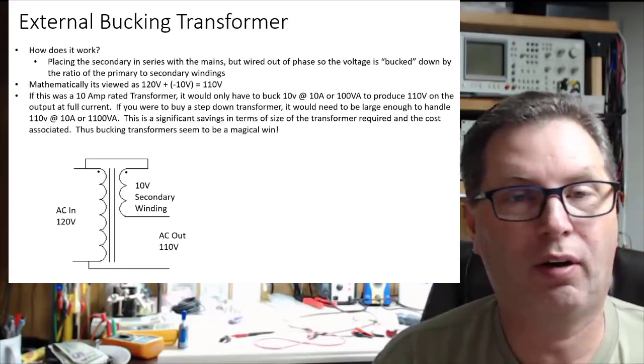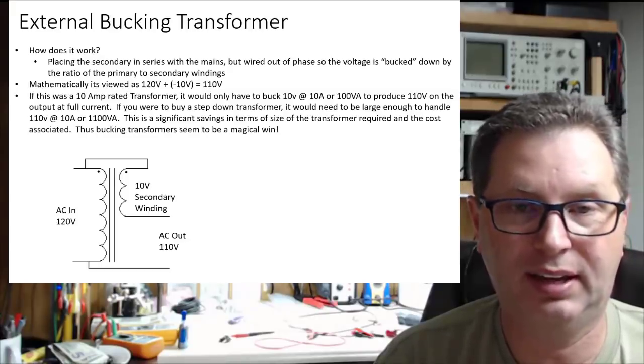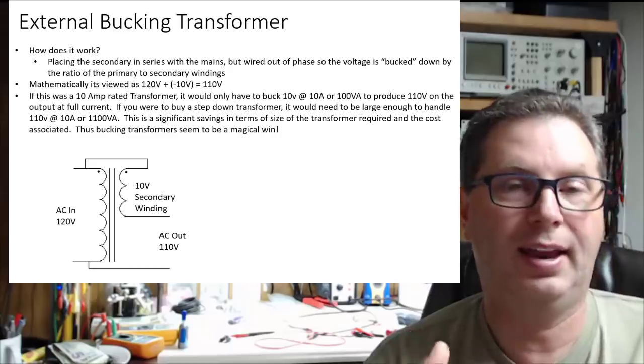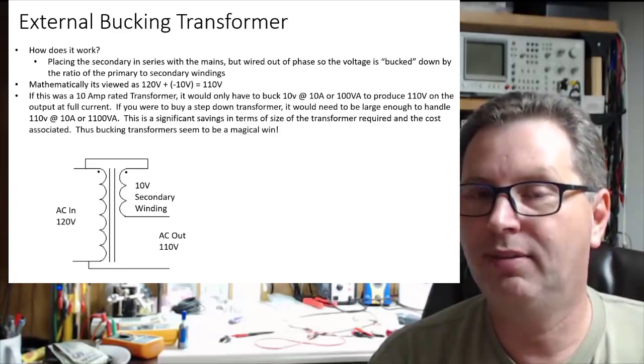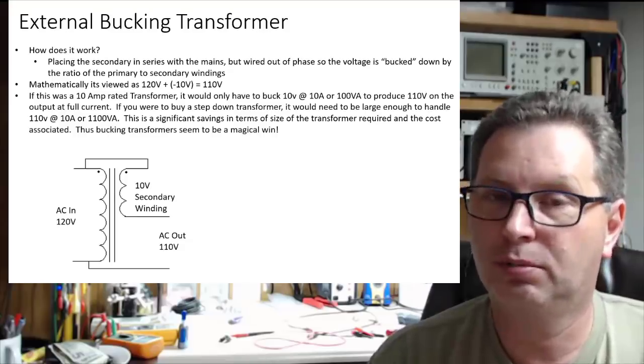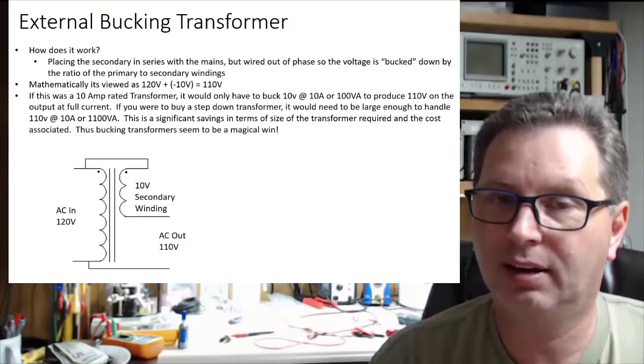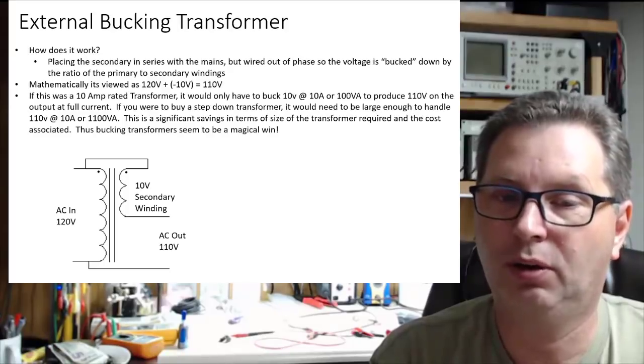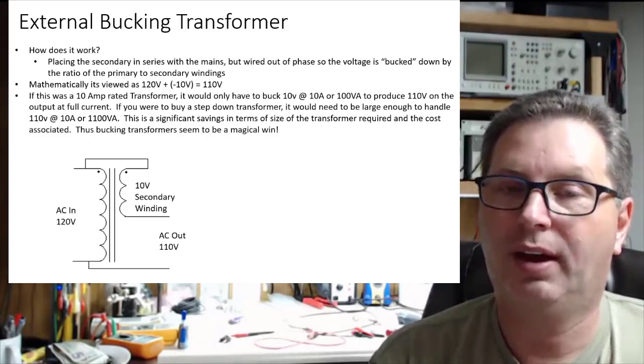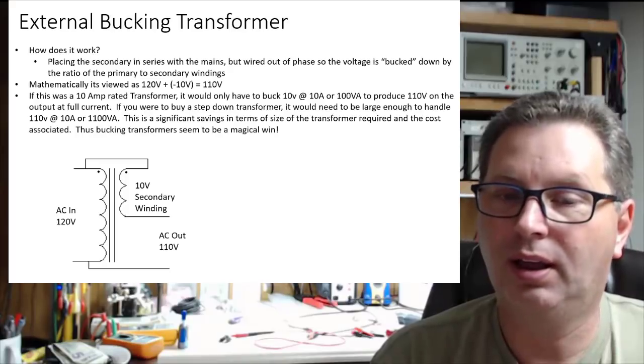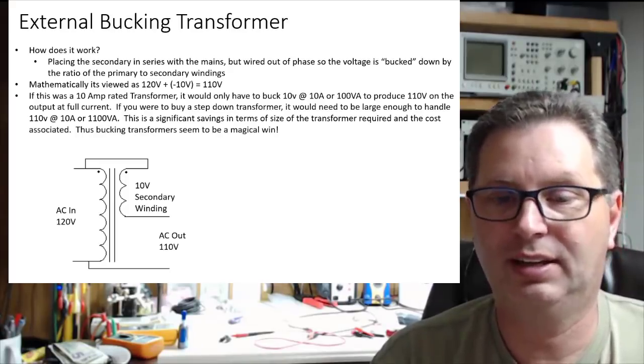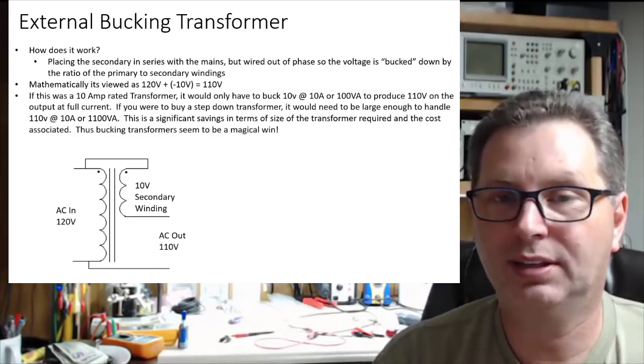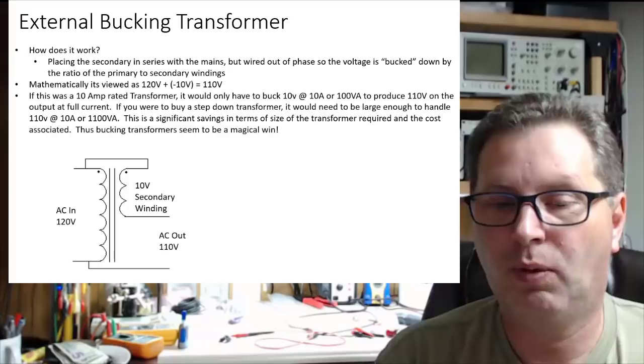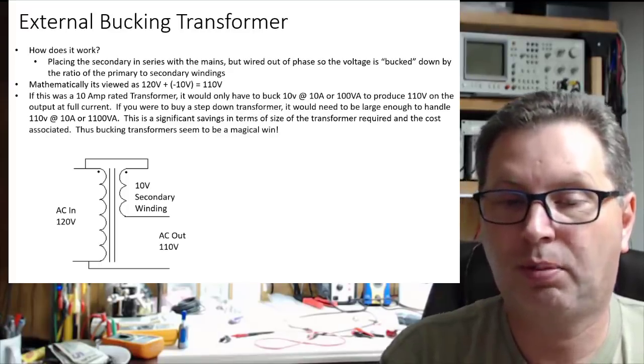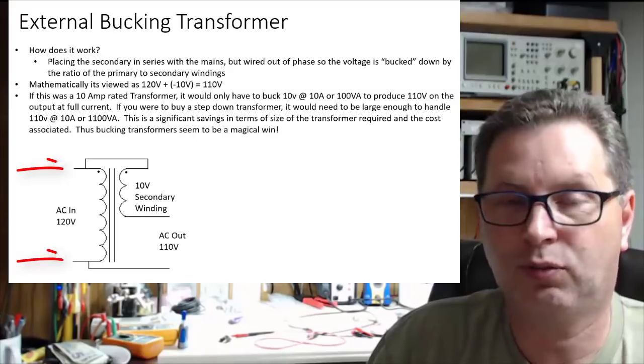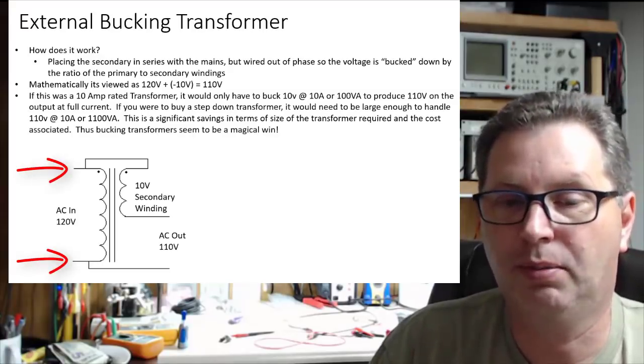We talked earlier about what happens when something is out of phase - it starts to add, at any given point on that waveform, the sum of those two points. If it's out of phase, it's likely negative relative to the primary winding. So the way this gets viewed is we've got 120 volts into this thing plus minus 10 volts because it's out of phase, ultimately giving you 110 volts out in this scenario. You wire this into your primary transformer just like any other transformer, with two leads that go back to your wall input.